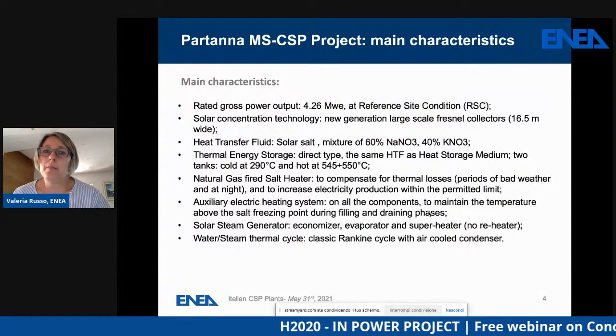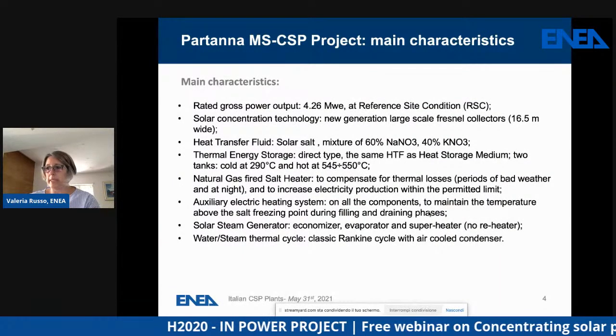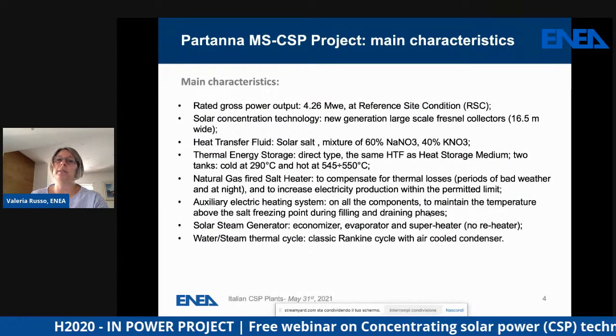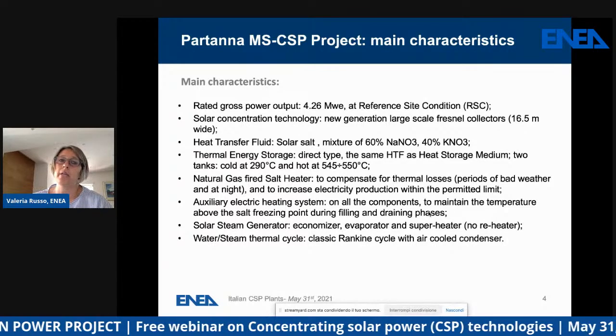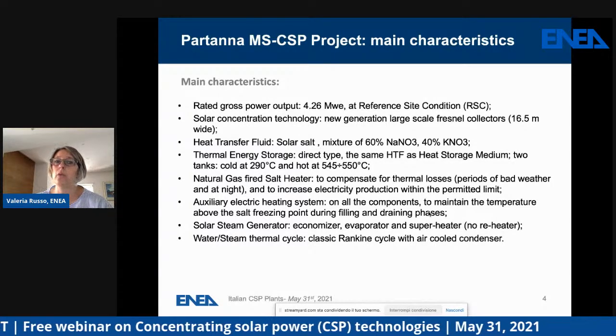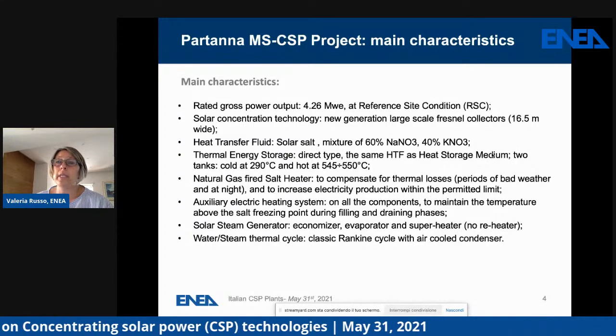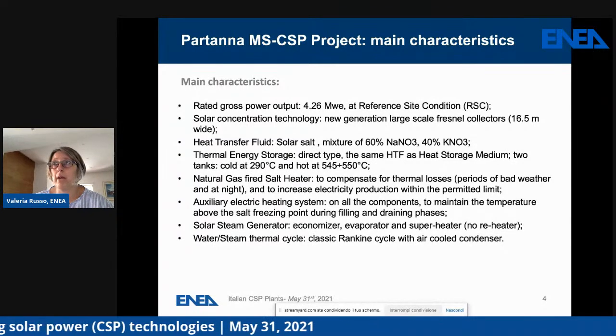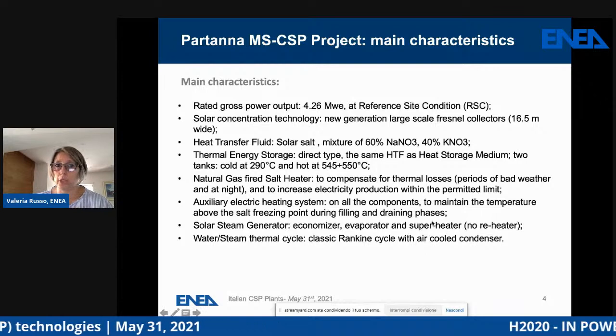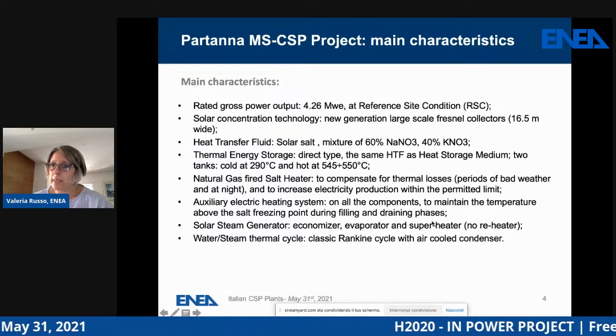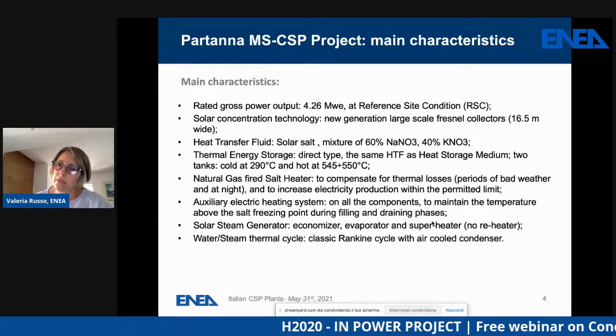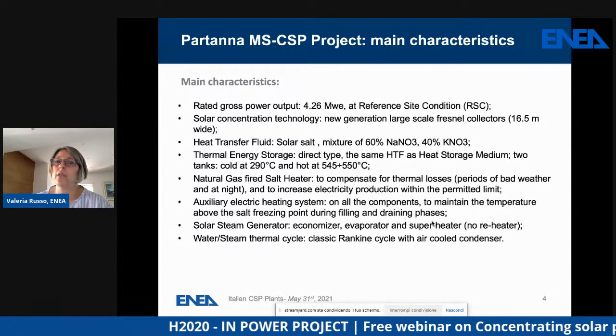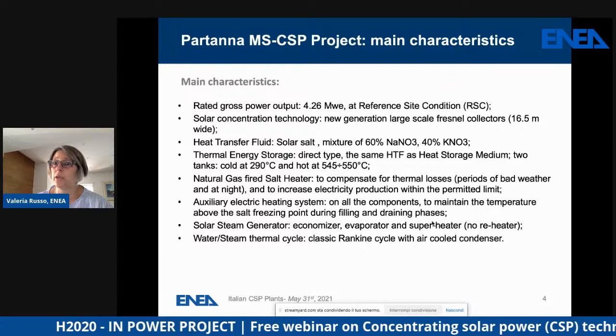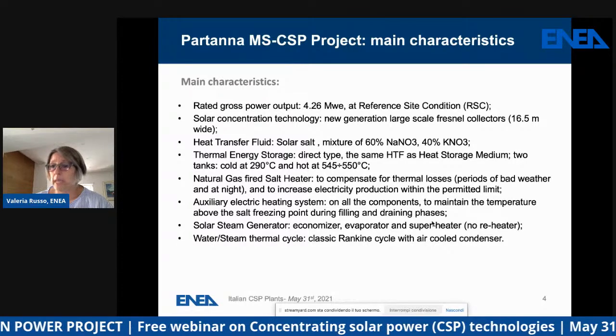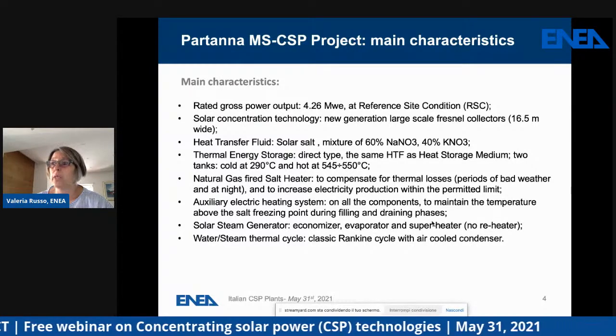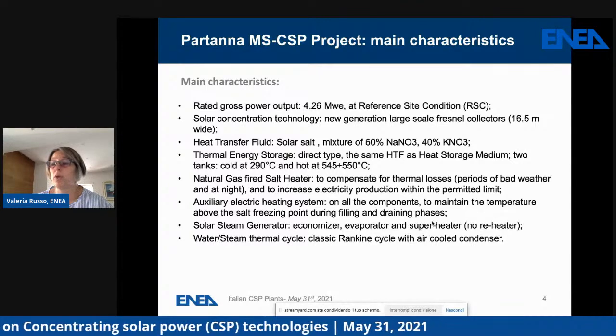Here we can see in more detail the main characteristics of this plant. The gross power output is equal to 4.26 electric megawatts at reference site conditions. The solar field's concentrator is based on the new generation of Fresnel collectors at large scale, with the width of the concentrator equal to 16.5 meters.